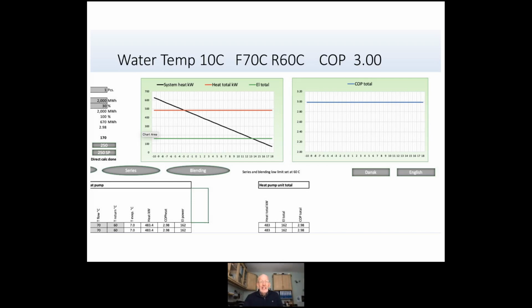Now, if we change the flow and return temperatures, we're beginning to see the impact on the efficiency of the heat pump. Here we still have the water temperature at 10, that has remained constant. We have a lower flow at 70, a lower return at 60, but we now have a COP of 3. So we're beginning to head in the right direction with COPs, and that is only being affected by the flow and return temperatures of the system. All the other aspects of these heat pumps are consistent. There's nothing else that's changing.